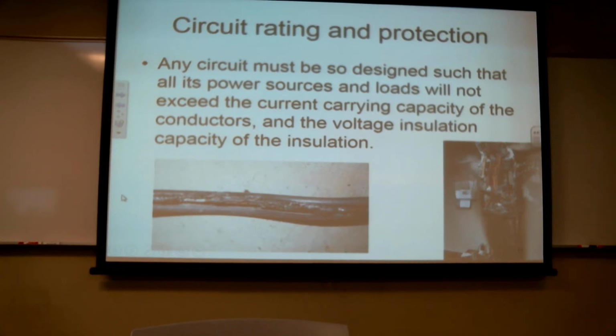For example, if you look at the wiring diagram, they sort of show all the lines as being the same size. But this guy right here is 1,000 kilovolt amps, and through here, 1,600 kilovolt amps. Then this is going to be a big heavy duty bus. These are going to be a little bit smaller coming out to individual circuit panels. Then the wire gets smaller and smaller.